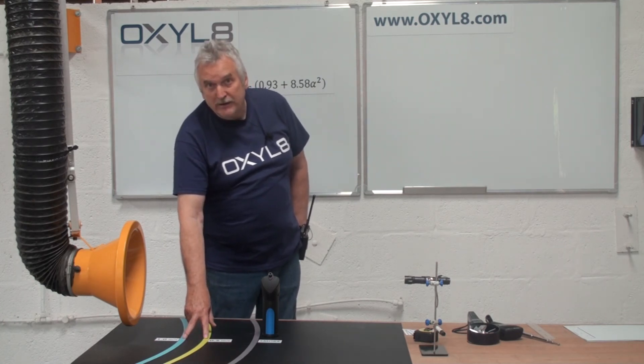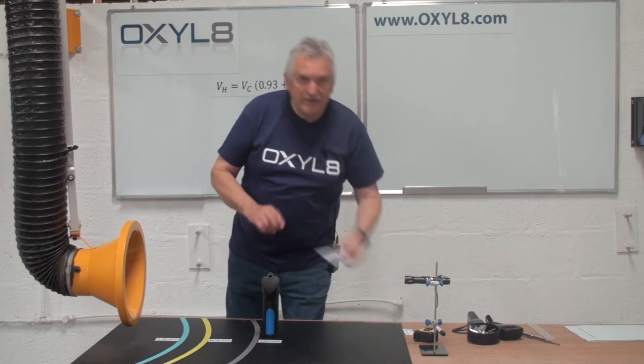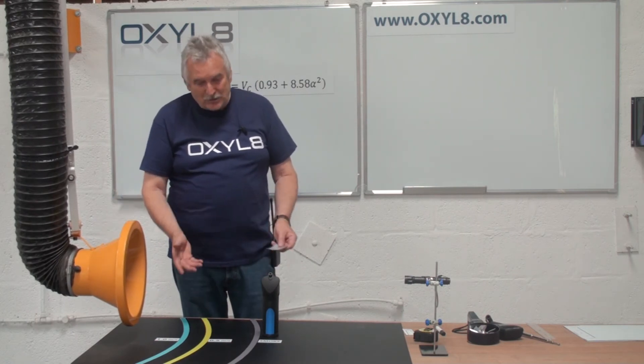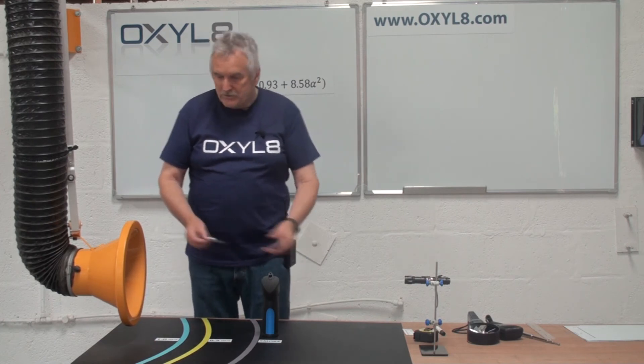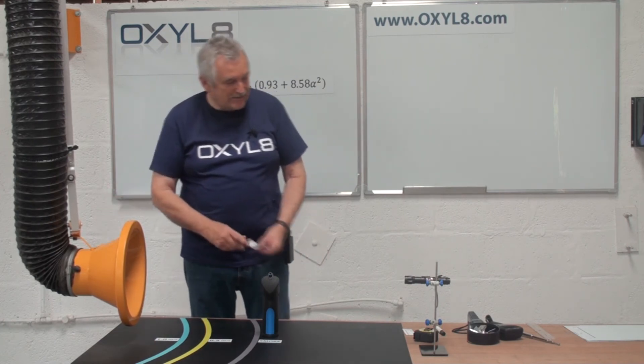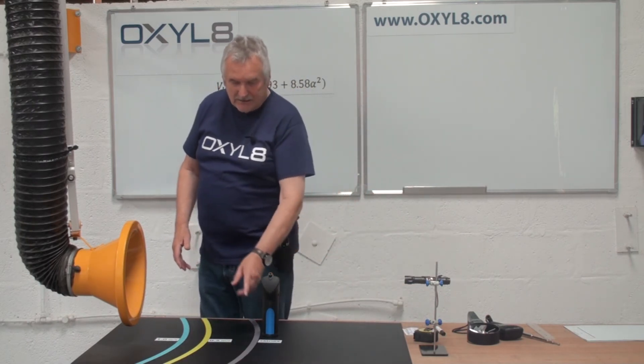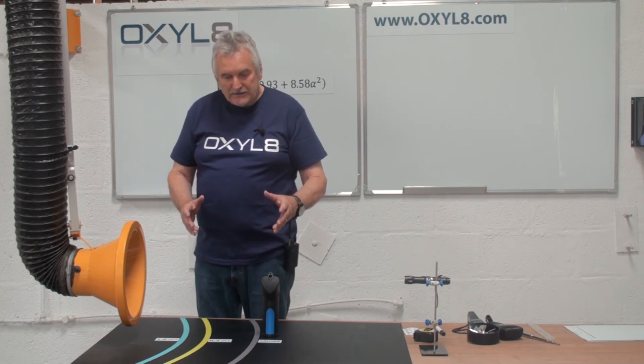I would prefer that you use these for your label that you will eventually put on the hood. Now that's a little bit controversial because we've always used smoke. People will use the smoke, put the smoke on here, but the danger and the difficulty I have is that as we've seen, the smoke will go further in still air conditions and will tend to give us a false indication.